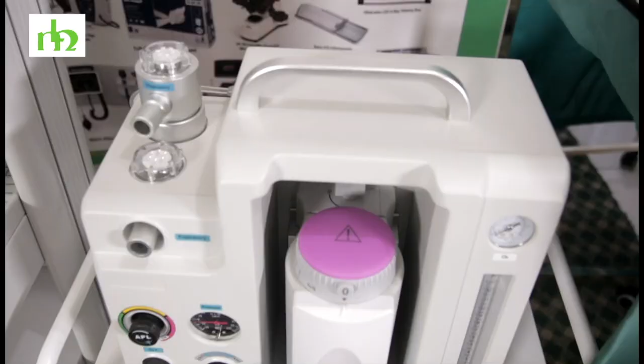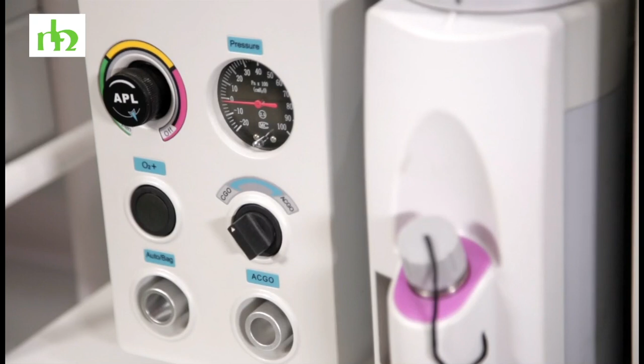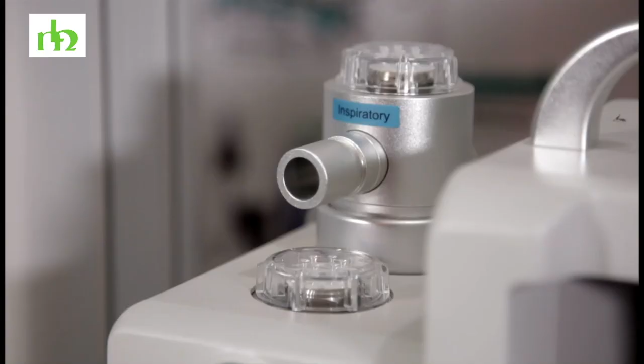Next to that is the portable anesthetic machine. This is a mobile type of anesthetic machine. It has the oxygen flow meter and 1 vaporizer. So your APL valve has color codes for you to see the safe zone from going to yellow to red on the APL valve. And this can be moved around by the anesthetist in order to be used anywhere on the field, in a remote area, and what have you.